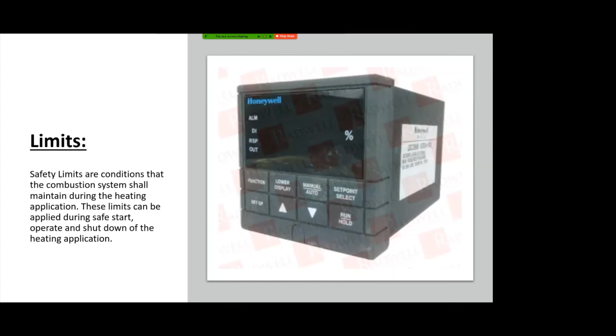So UDC, I'm sure a lot of you are familiar with this piece of hardware. This piece of hardware has been around for forever at Honeywell. We have to use in combustion systems the FM approved version of this controller to provide most of the times like high stack limit. By code, it has to be an FM approved device for that service. Down here, safety limits are conditions that the combustion system shall maintain during the heating application. These limits can be applied during safe start, operate, and shutdown of the heating application. So they're a requirement, and the devices that you use to accommodate those requirements have to be approved for that service. That's the point I'm trying to make here.